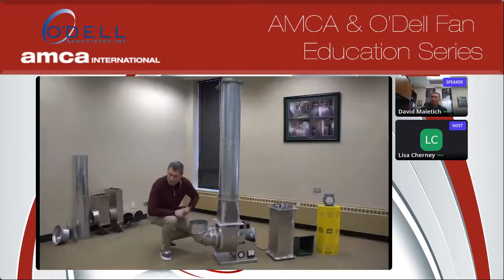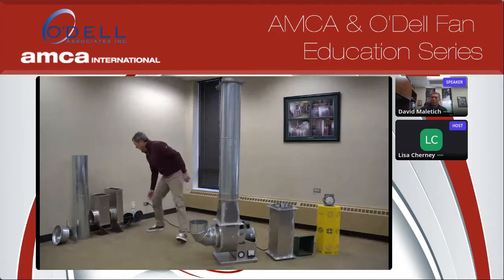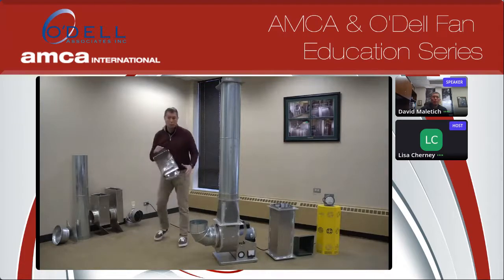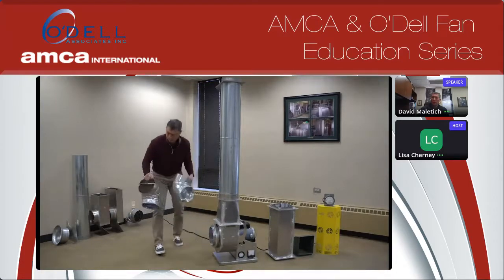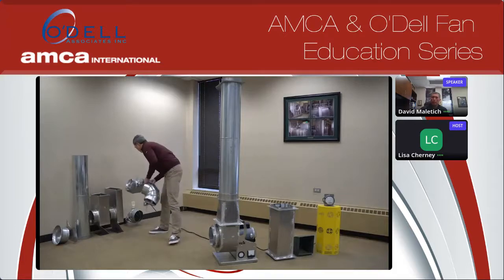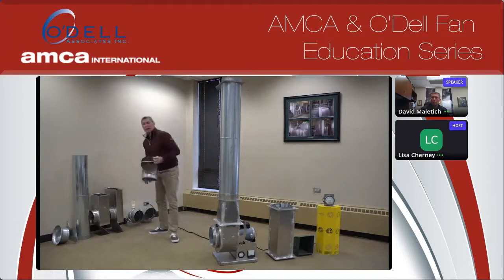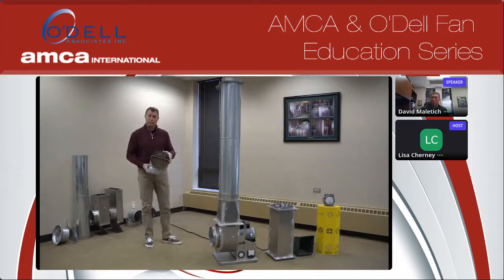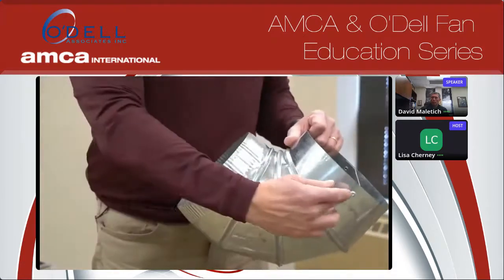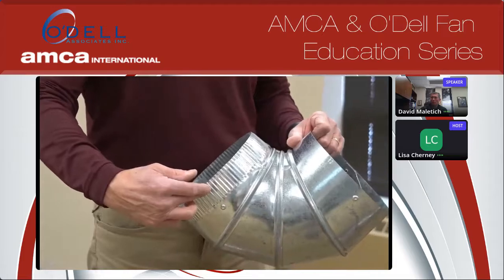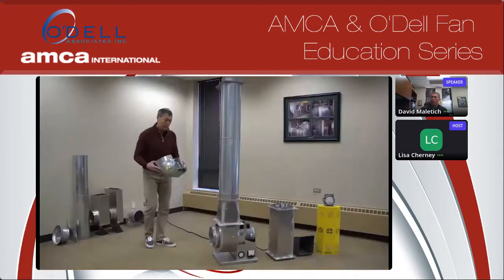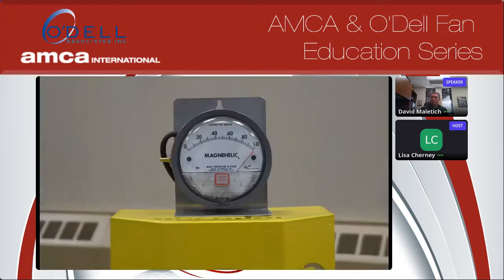Now the next thing we're going to do is add an elbow, take off this one here, and we're going to add an elbow that has a turning vane in it. And that turning vane basically splits the duct into two sections. So when we put it on here, look at the Magnehelic, you'll notice that there is still a loss associated. However, that loss is much less than what it would be if we had an elbow with no vanes in it.